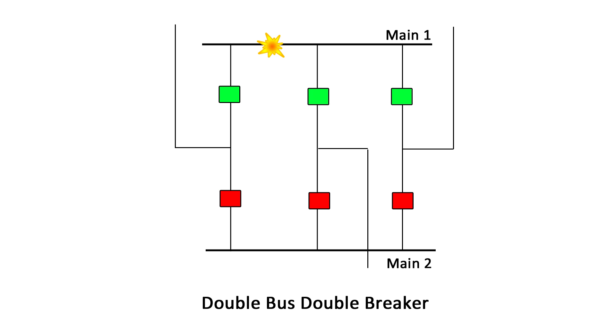Failure of one of the two buses will not interrupt the circuit because all of the circuits can be fed from the remaining bus by isolating the failed bus. Load balancing between buses can be achieved by shifting circuits from one bus to the other.